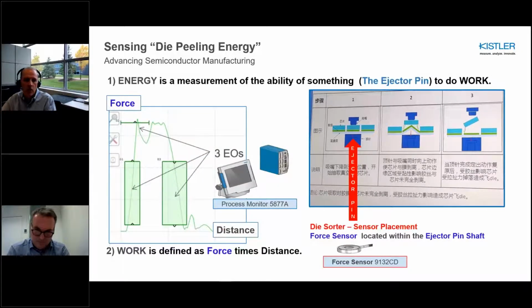On the left side, we view a curve that has pin position or distance plotted on the lower x-axis, and pin force, which is the effort encountered on the pin during its movement, plotted on the y-axis. The work performed in removing the chip from the membrane is the integral of this curve, or more simply stated, as the area under the curve. The process monitors are utilized to track both these parameters and provide a detailed signature of the process. A pass-fail toolbox included within these monitors provides for waveform evaluation as well as reporting traceability tied to each die removal.